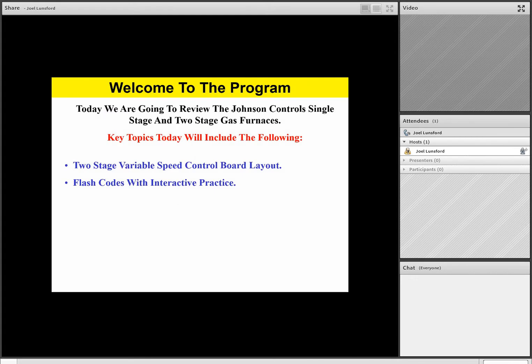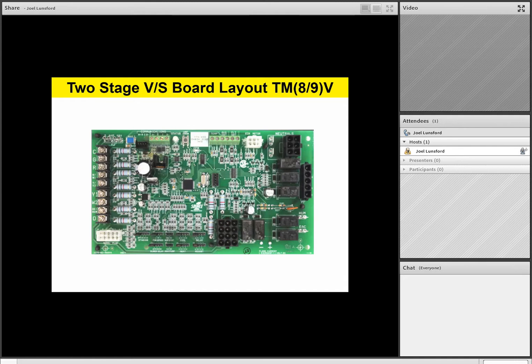Key topics we're going to be talking about today will be a two-stage variable speed control board, and then we'll do some flash codes with some interactive practice, or more specifically, to give you the opportunity to look those up in your workbook or your handouts. So let's take a look at our two-stage variable speed control board. An example where this board would be found would be in a TM9 or a TM8V, V for variable speed. Now remember, team, a variable speed blower is another type of ECM or high efficiency blower. The main difference is it's going to have a control board and some jumpers on there that we can select our airflow with, instead of having to physically move an airflow tap on the motor itself.